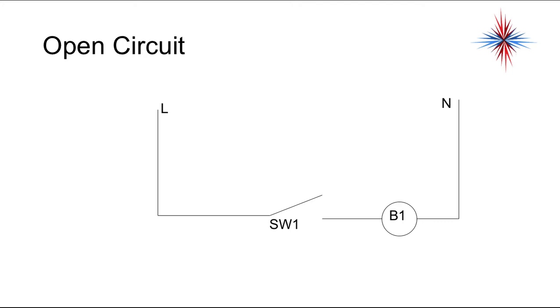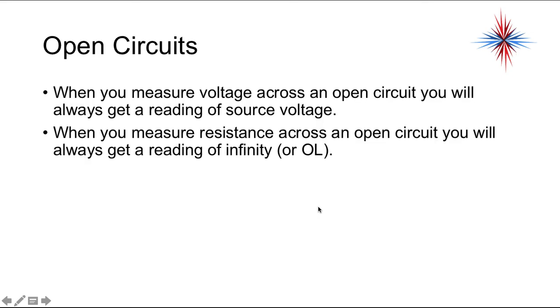So this is an open circuit. The open is at the switch 1 or SW1. That switch is not closed. There is a gap right here where the current cannot flow. When you measure voltage across an open circuit, you will always get a reading of source. When you measure resistance across an open circuit, you'll always get a reading of infinite, or OL, on most digital meters. All that means is the circuit is open.